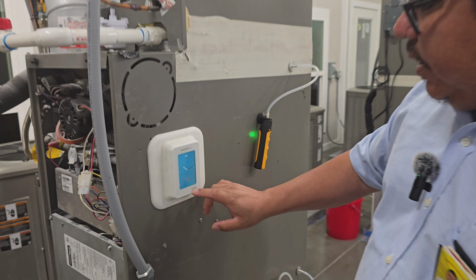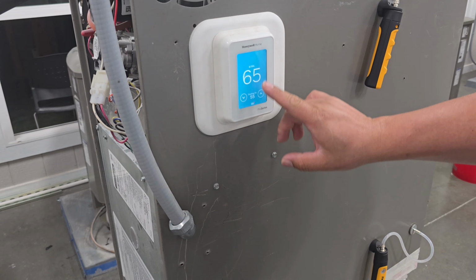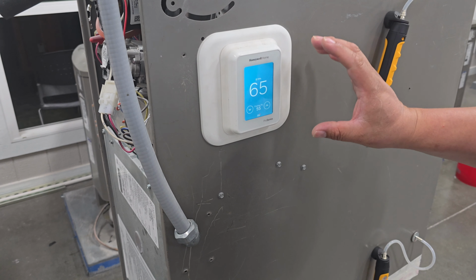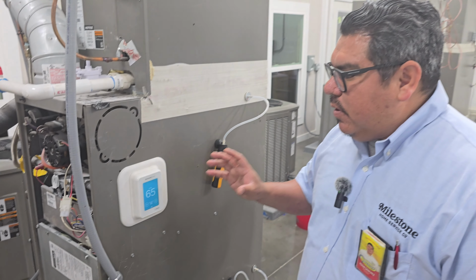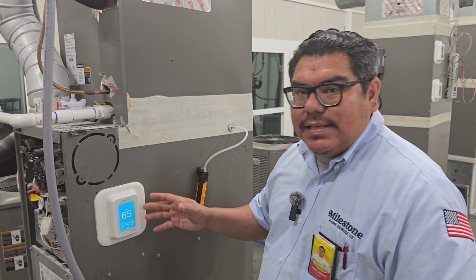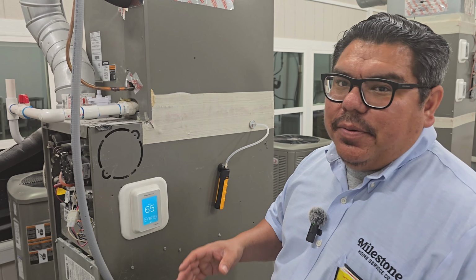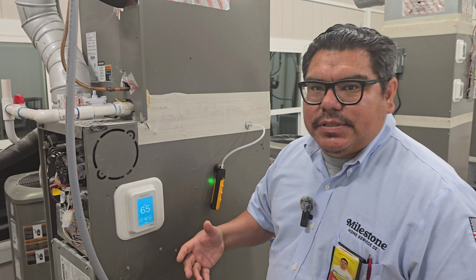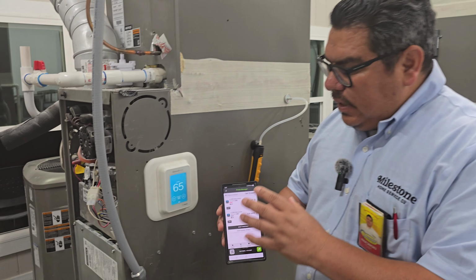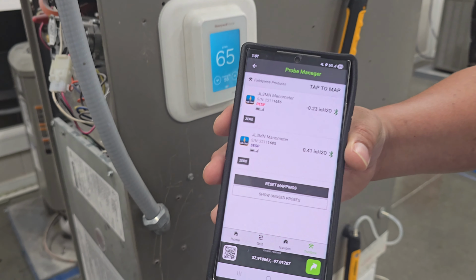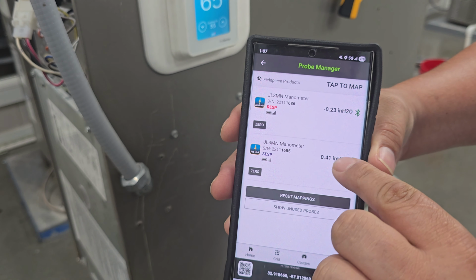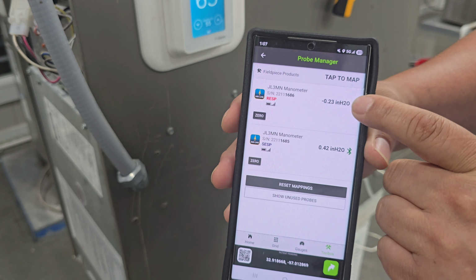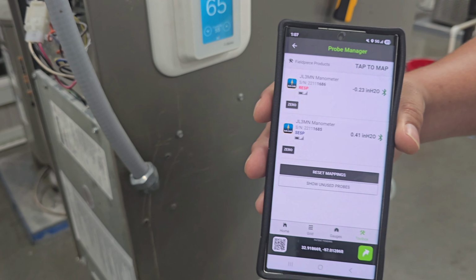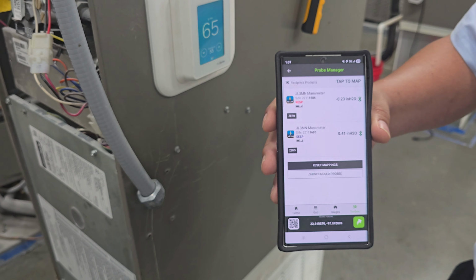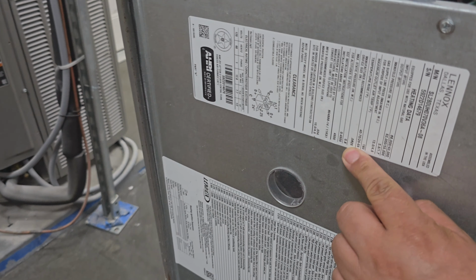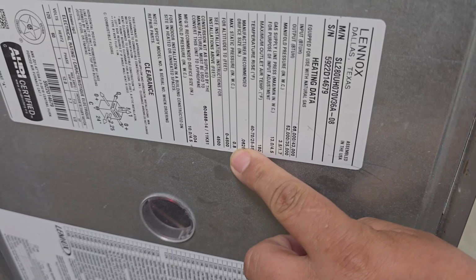Next thing is we're going to go to the thermostat and make sure that it's dropped down pretty low. And the reason we're doing this is that if the system goes at 100%, or in this case, second stage, in communicating, you're going to put it on test mode, and that way it runs at 100%. And that'll give us the proper static pressure. So right now we're at 0.41 and 0.23, so that gives us 0.64. And right here on your data tag, even on air handlers, it'll tell you what it's set for.